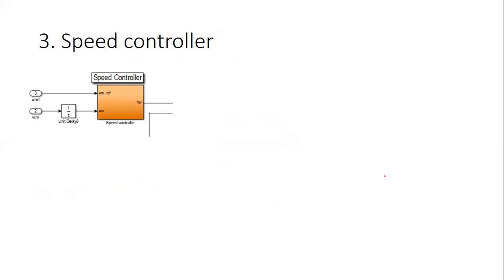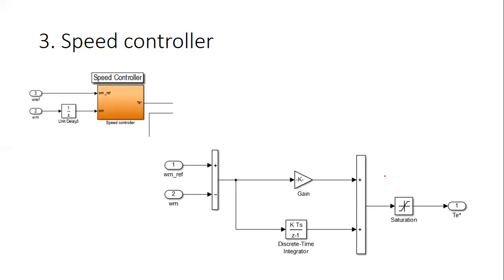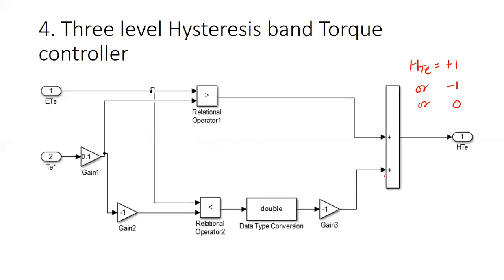The speed controller is a PI controller. Electrical drives have mechanical equipment that takes time to respond, so the PI controller gives better dynamic performance with high steady-state accuracy. The saturation block after the PI controller sets the maximum torque at which the motor should accelerate or decelerate in case of large positive or negative speed error. The Kp, Ki, and required torque command are all handled by this PI controller with saturation block.